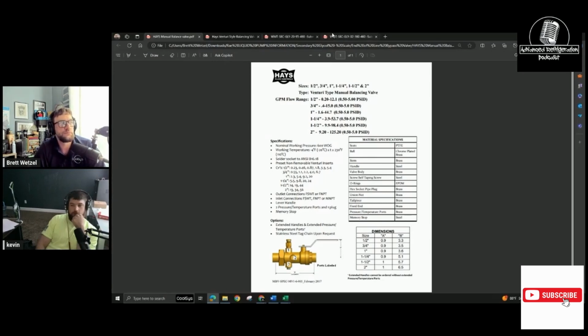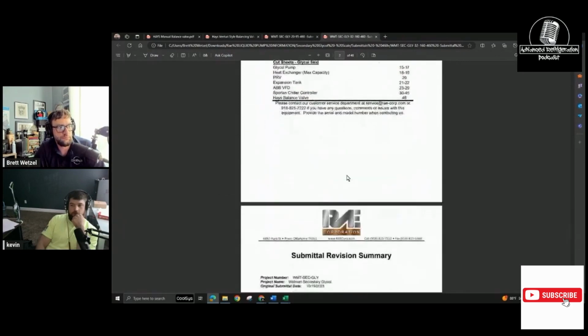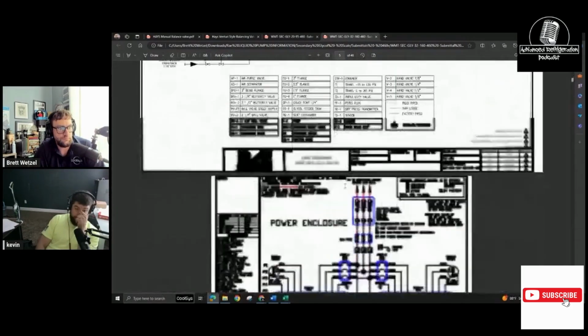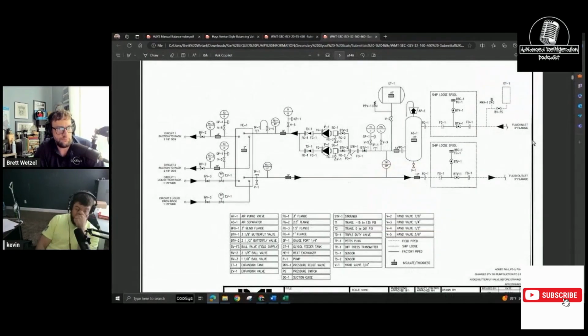So all these VFD pumps are controlling off of that flow, and the balancing valves are all like 3/4 or halfway cocked. I haven't quite messed with it because at one point this building was balanced. So I haven't messed with it yet. We're going to do the fill and flush next week.